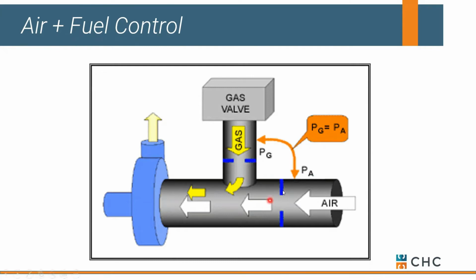Now, I know this slide's a little fuzzy, so please forgive me. Don't focus on this too much. But what you'll see here is the manufacturer's got some fixed orifices, one for the air and one for the gas. It's typically 10-to-1 ratio between air and gas. So these orifices tend to be fixed to help maintain that ratio. And what you'll find is that a gas valve is set up as, we call it negative regulation, but basically it's along for the ride. It's reacting to the pressure difference on the air side.